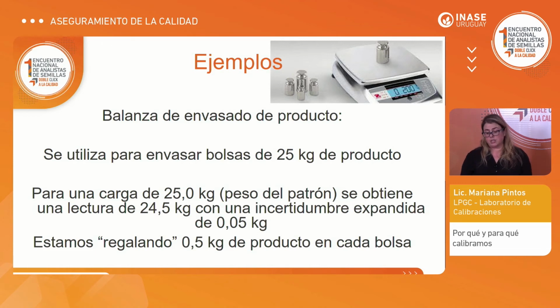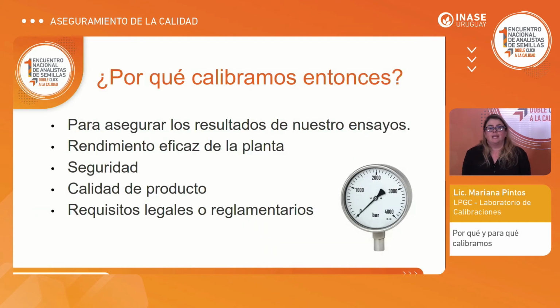Another example could be a scale to pack a product. Here you are packing 25 kilo bags. When we calibrate and we put a 25 kilo weight, we read 24.5. So when we are loading the bag, we are loading 25.5. We are giving away half a kilo of the product. If we put the standard weight and it reads 25, when we go to 25, we are missing half a kilo. So this could mean that we get a complaint, a non-conformity, or the customer is not satisfied. So for all these reasons, it's important to know what we are measuring.